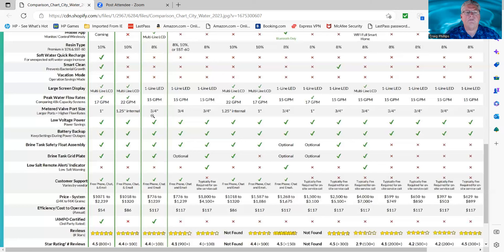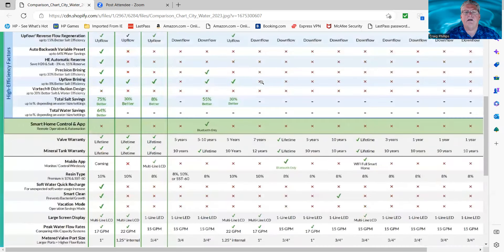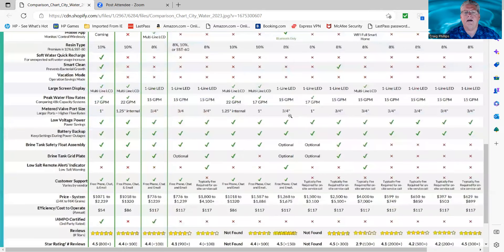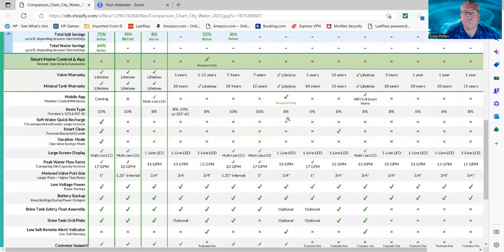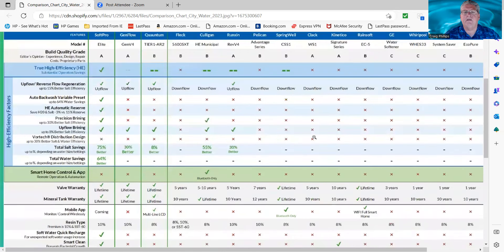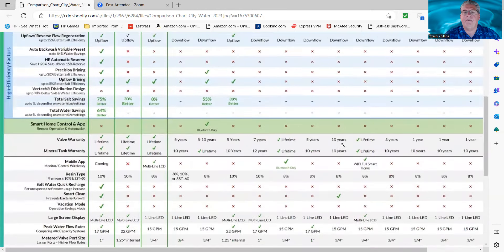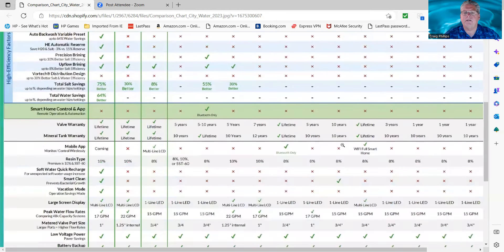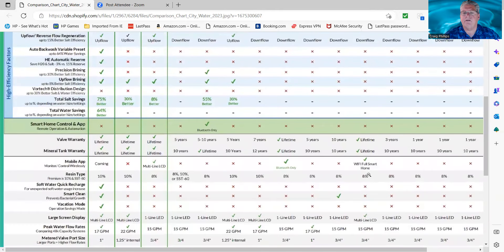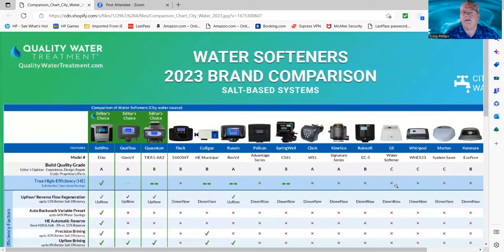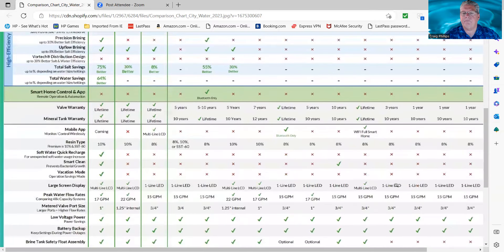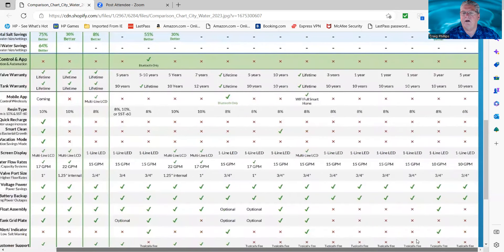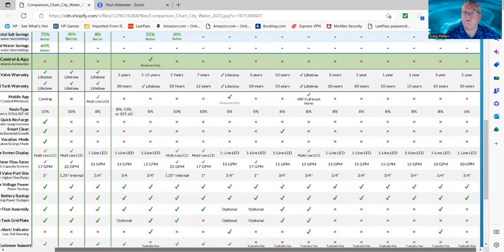The Quantum is 15 because it's a three quarter inch valve. The Fleck, same. When you get to the Culligan, it's the same. The one inch valve here is going to be the Pelican. You're going to get 17 gallons per minute. Springwell is a three quarter inch valve, so you're going to get 15 gallons per minute. The Clack is 1.25 inch. The Kinetico is three quarters, so you're going to get 15. Rainsoft, three quarter inch, so you're going to get 15 with that. The General Electric is 15 gallons per minute peak. And then you drop down to 10 gallons per minute on these other systems because the distributor tube size is smaller than three quarter inch.